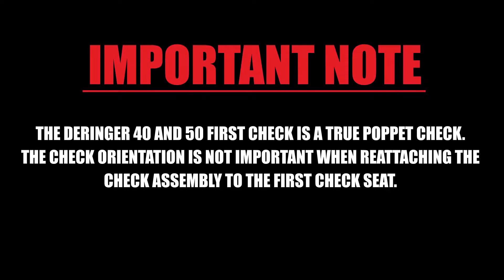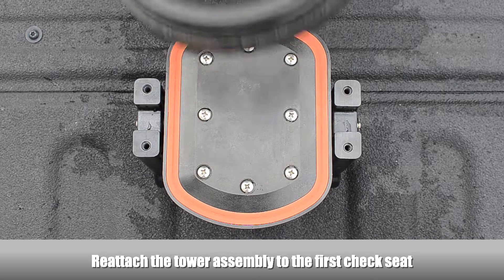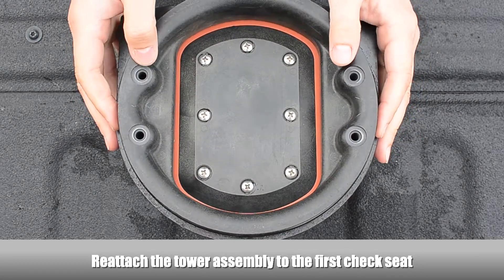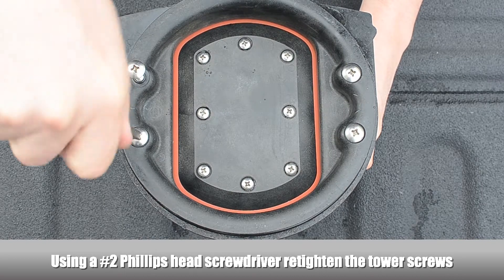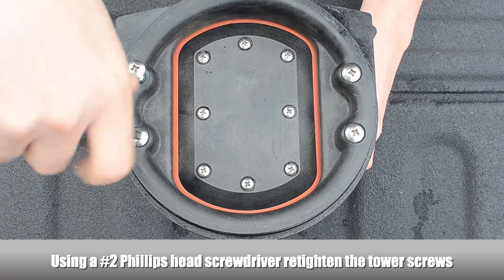The Deringer 40 and 50 first check is a true poppet check. The check orientation is not important when reattaching the check assembly to the first check seat. Reattach the tower assembly to the first check seat. Using a Phillips head screwdriver, re-tighten the tower screws.